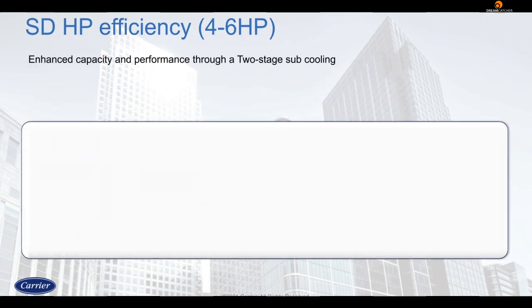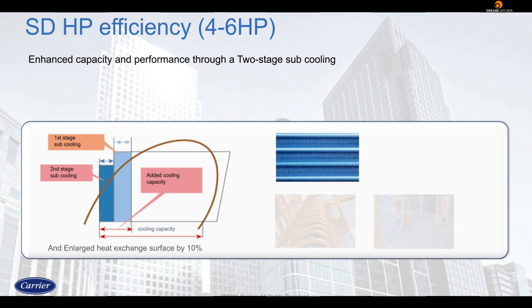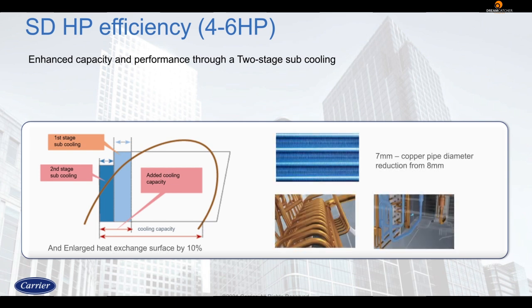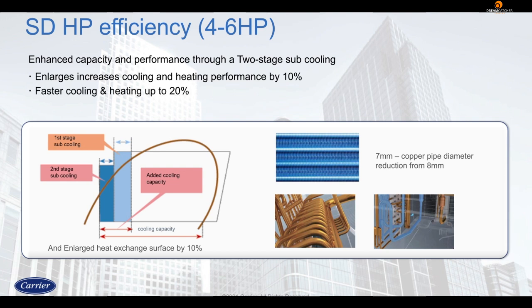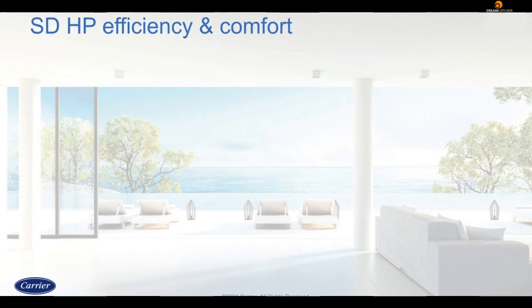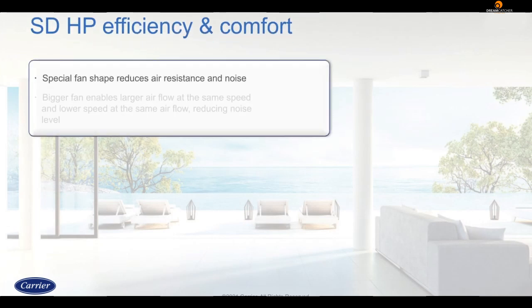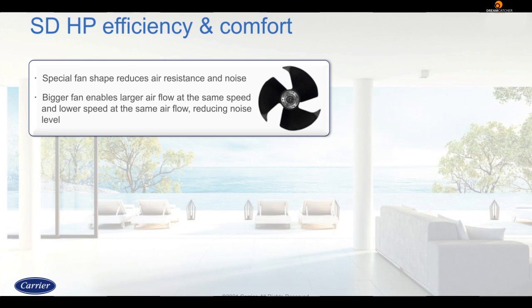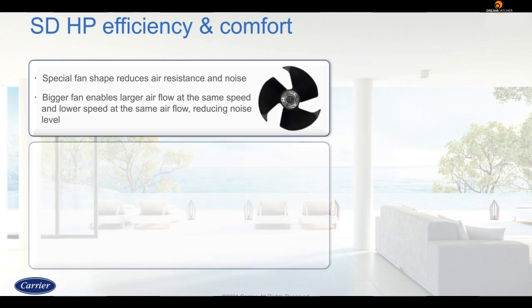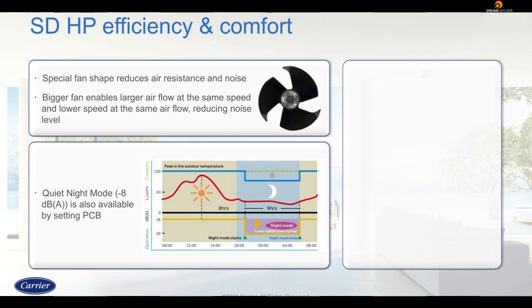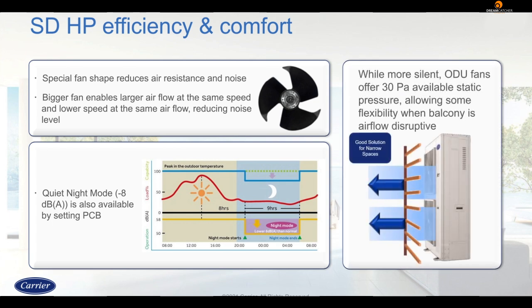The 4 to 6 horsepower side discharge heat pump system comes with a 2-stage subcooling system. It increases cooling and heating performance by up to 10% and allows for faster cooling of up to 20%. Not just that, it also eliminates refrigerant noise in the transition phase. The side discharge units also feature special fan shape for larger airflow at the same speed, which reduces noise, and there is also a quiet night mode in the PCB that reduces noise by up to 8 decibels.